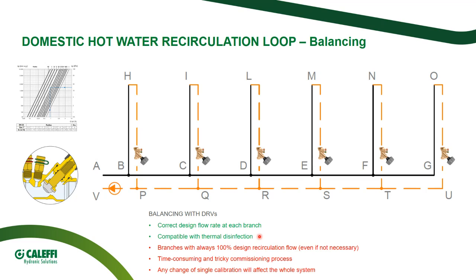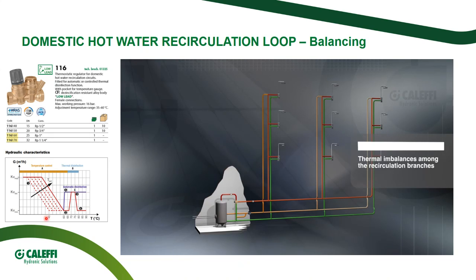not easy. And also, in the last years, people are paying a lot of attention to energy waste, and this is our case also in Europe, but also in the GCC, especially in Dubai. So green buildings and low consumption buildings are more and more appreciated. So when you install and calibrate the DRV, they work, but they are not able to modulate, so to throttle, to reduce the hot water consumption when it is not needed. And it is something that the thermostatic balancing valve can do.